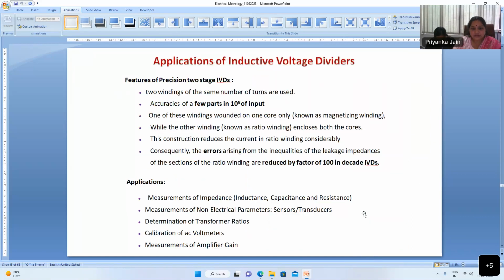So these are the applications. It is used for accuracy of a few parts in 10 power 8. With the magnetizing winding and ratio winding, when there is very little ratio current, we are getting a very precise voltage ratio for impedance measurement. The construction reduces the current in the ratio winding considerably, and error arising from the inequalities of leakage impedance or the section of the winding is reduced by a factor of 100 if we have two-stage core construction. So these are some IVD features which we are using in impedance measurement.